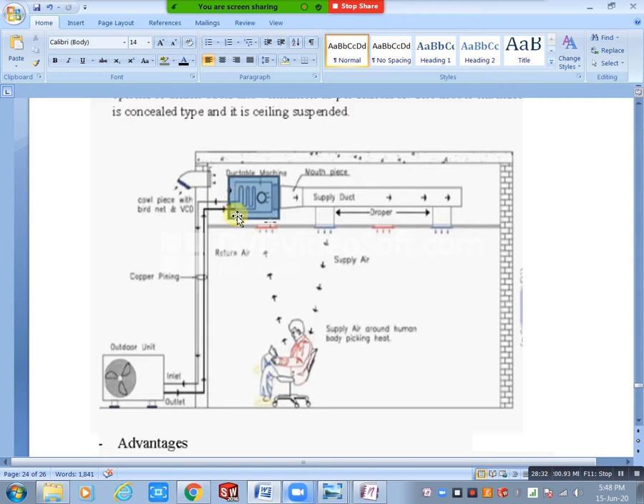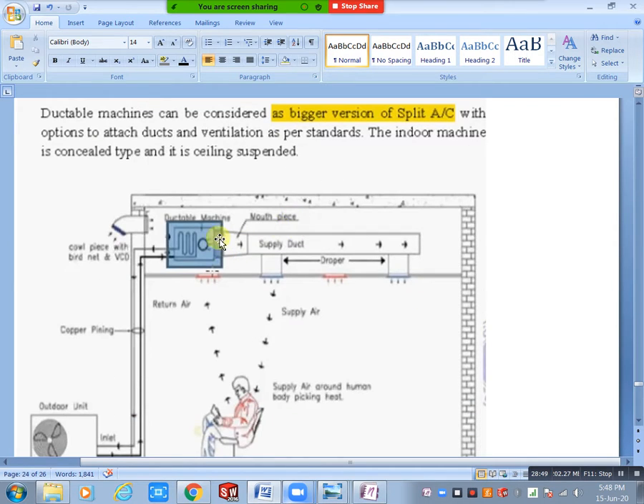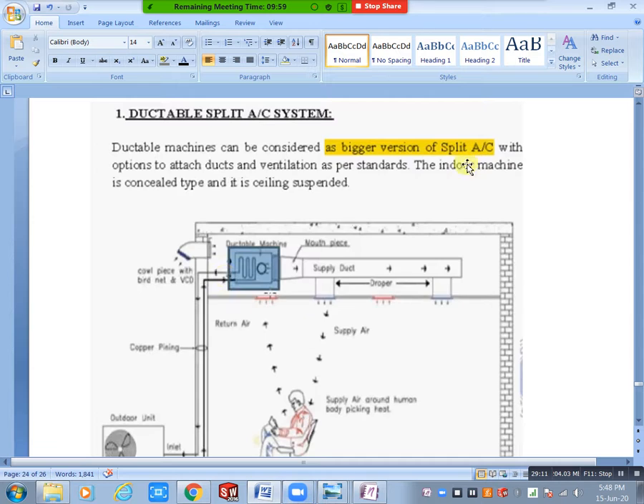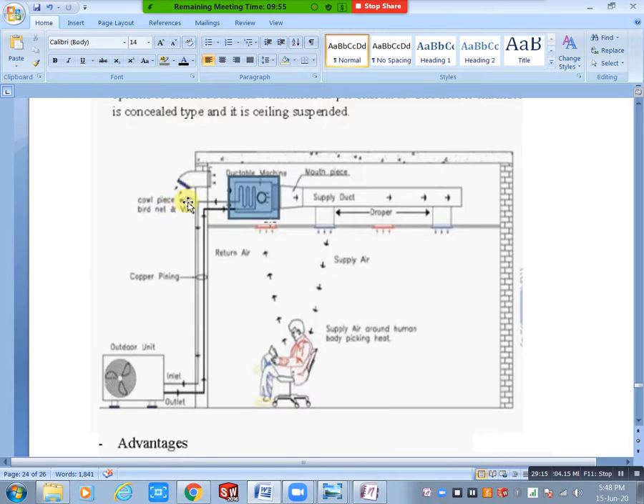You can see a zigzag portion — that is a flexible duct. Between the machine and the duct, we have a flexible connection. Also, there is a wall opening for ventilation — that is the cowl piece with a net. As a thumb rule, we need 10 to 30% of outside fresh air, and the remaining 70% is return air.